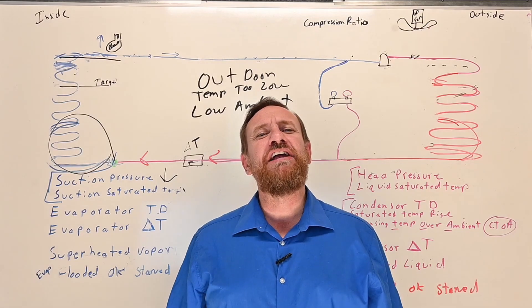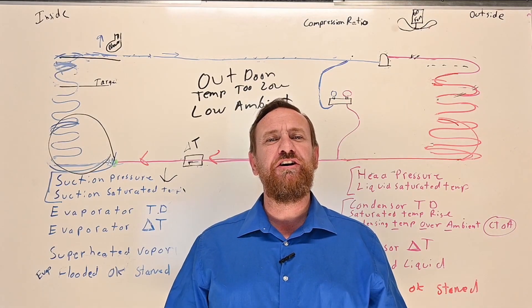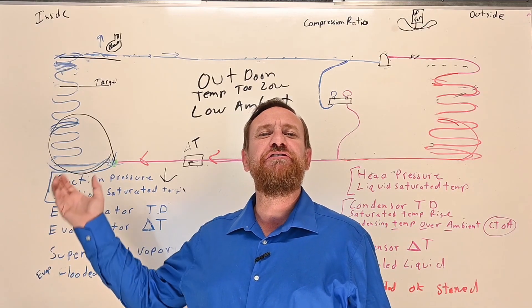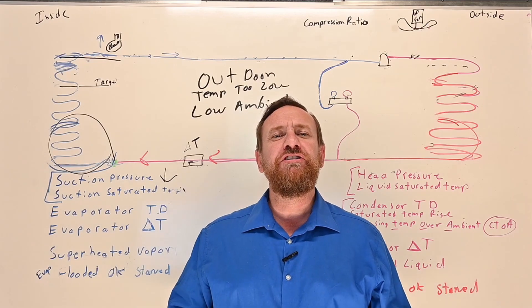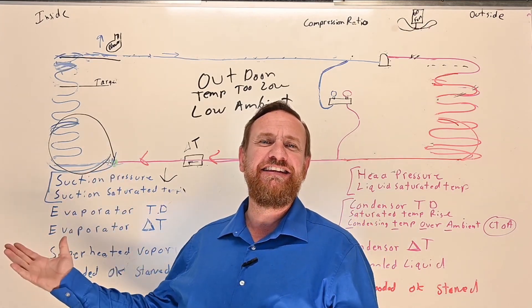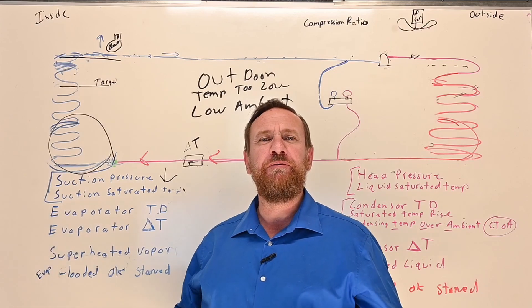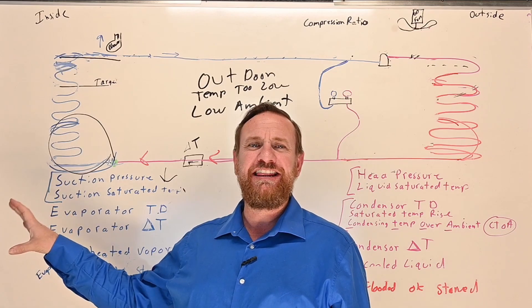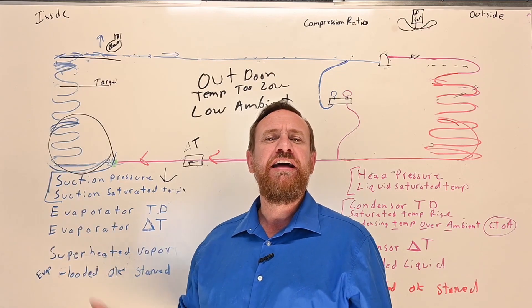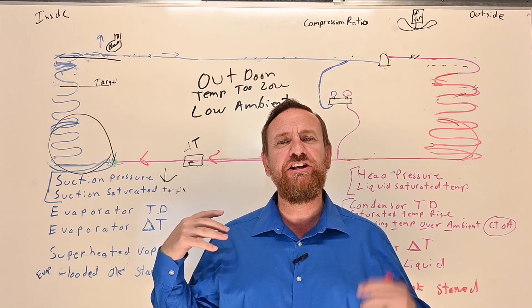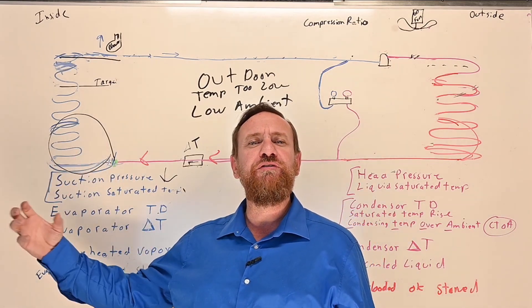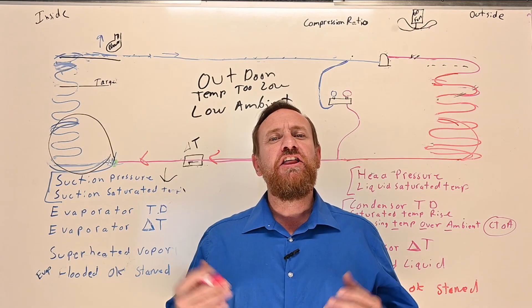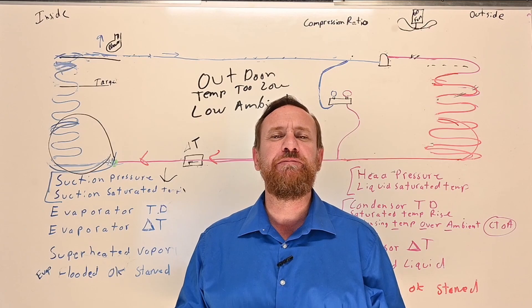At some point in time, you're going to have to service an AC system when the temperatures are very low. The outdoor temperature is going to be low, and even if your indoor temperature is not that low, it's going to very quickly change that. So what we're going to start with is the indoor. What we can do is add heat into the house. If we heat the house up, whether it be using the heat pump or the furnace, electric heat, whatever it takes, but put a heat load inside of the house. So that way we have some heat to take out. They have a limited amount of time to do this because as we run the air conditioner, it's going to very quickly move the heat from inside the house to outside the house. You got to think about it being a low ambient condition. The heat's not naturally coming back in like it would in the summertime.